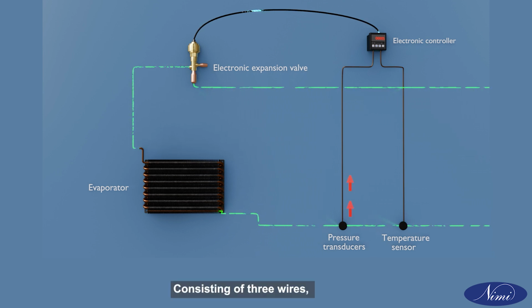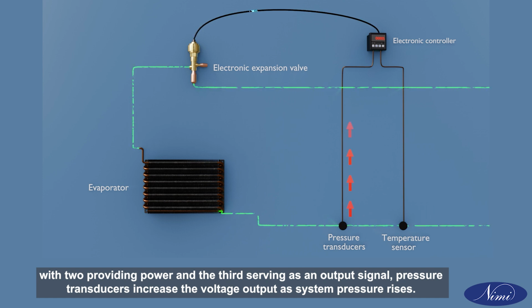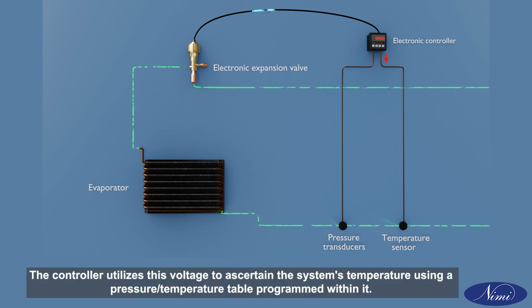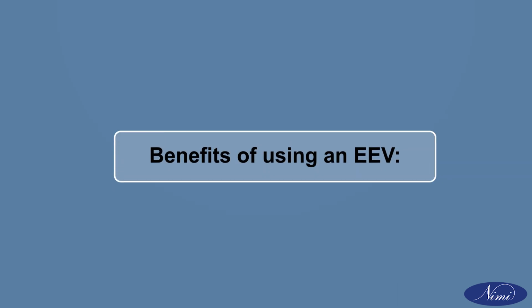Consisting of three wires, with two providing power and the third serving as an output signal, pressure transducers increase the voltage output as system pressure rises. The controller utilizes this voltage to ascertain the system's temperature using a pressure temperature table programmed within it. Benefits of using an EEV.